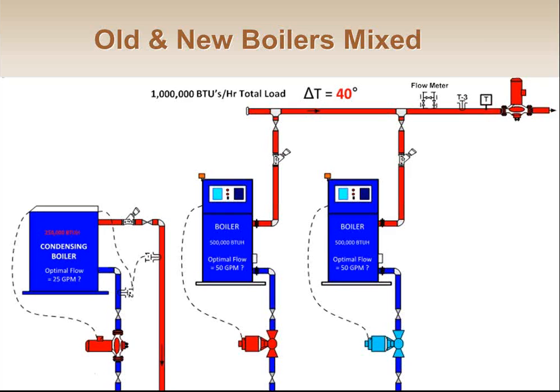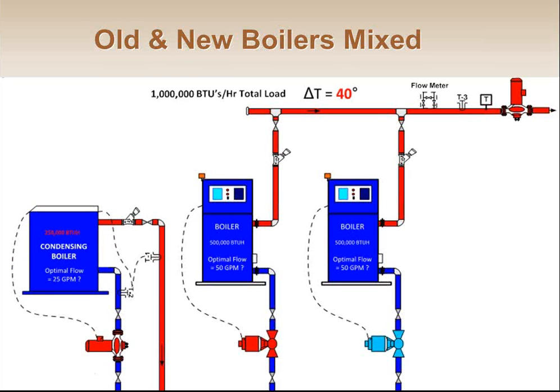So what we usually do in those cases, we recommend you mix it, right? So if my one boiler died, let's say I had 3 boilers here on this drawing, and one of them died, right? Instead of replacing him with another 80% inefficient boiler, how about I replace him with a condensing boiler? And in fact, I'm going to probably even downsize him because, once again, my plant was probably oversized. So I took the 500,000 BTU boiler out. I put this 250,000 BTU boiler in, and he's going to do most of my work most of my days. In fact, sometimes on jobs, we find that he does everything himself and the other boilers never kick on.